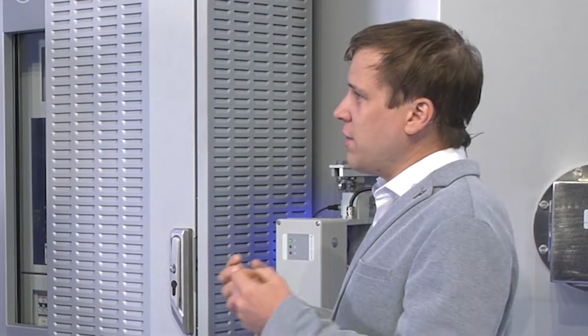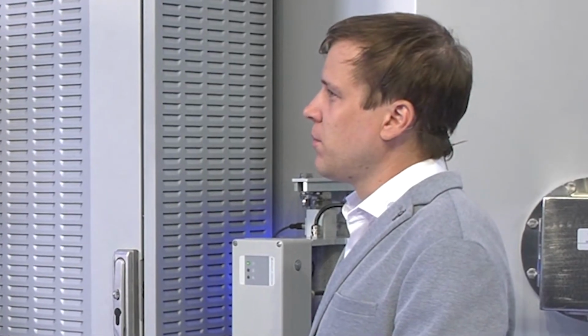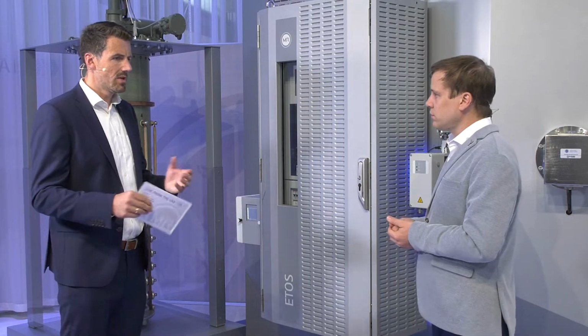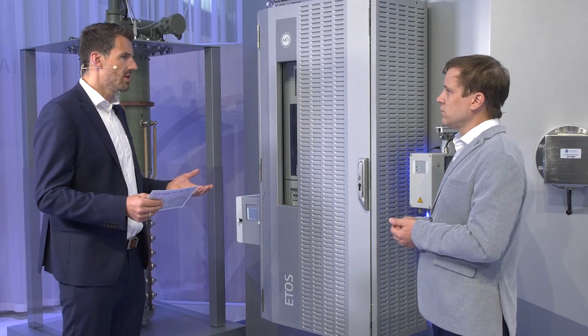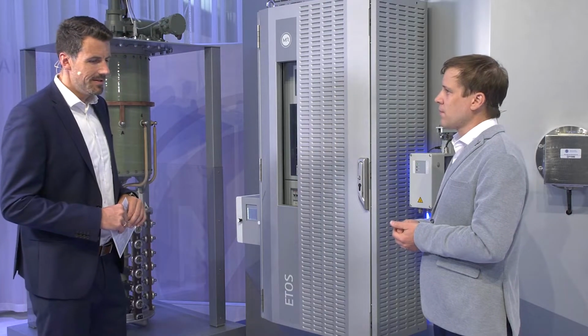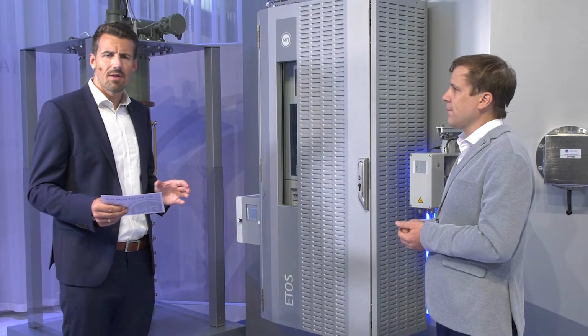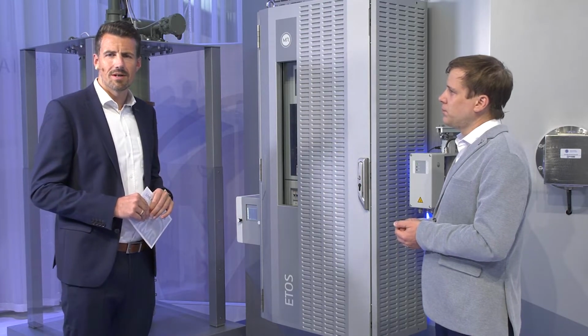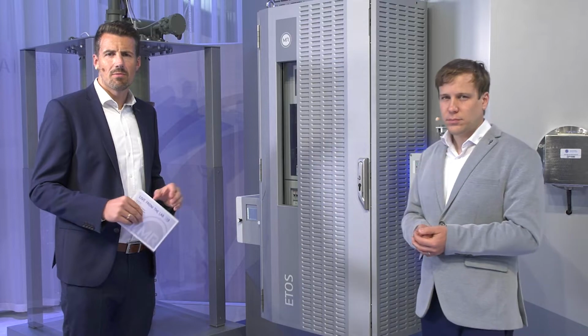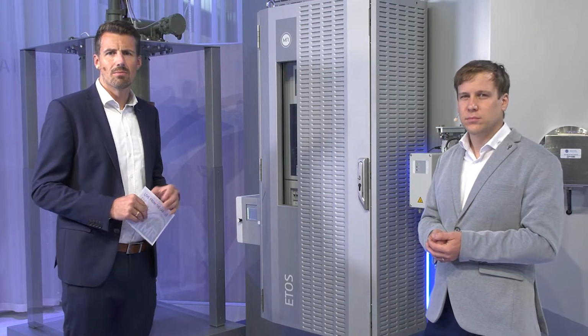If you want to know 100% how hot it is inside the winding, you need a fiber optic temperature measurement, like the MSense FO. Then you have these fiber optic sensors placed right in the winding, and they measure the exact temperature. So calculation or measurement is both possible here. Calculation, top oil, and measurement directly via FO technology. Exactly.